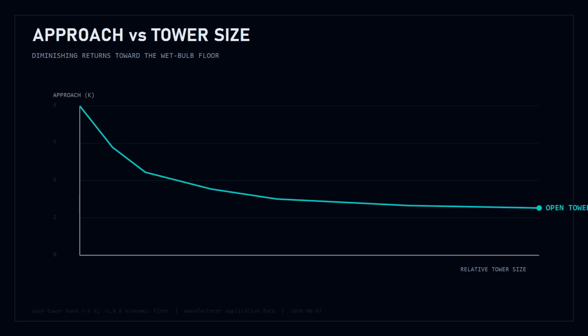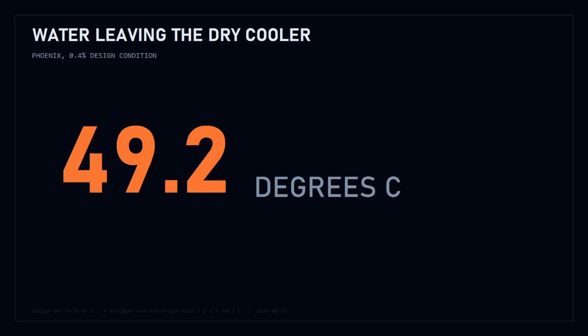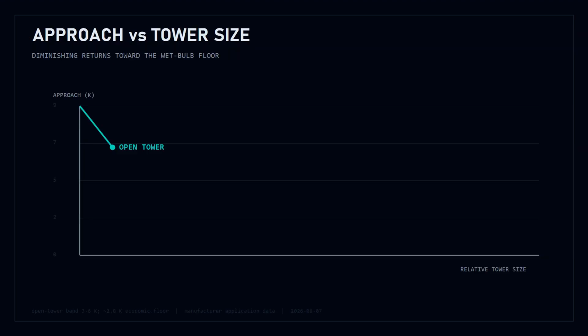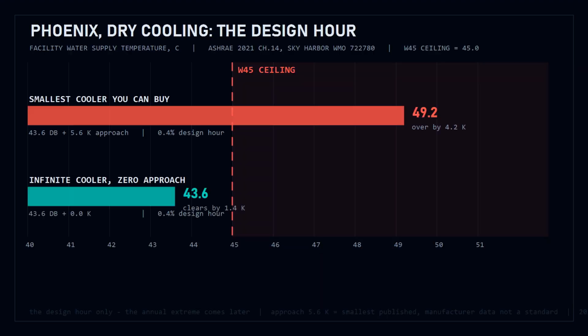3, and this is the one, Phoenix on dry cooling. Design dry bulb, 43.6. Add the smallest approach anybody publishes, 5.6, and you are at 49. Now, a bigger cooler does narrow the approach. Push it to infinity and the approach goes to 0, and you land on the dry bulb itself, 43.6. That clears W45 by 1.4 degrees.